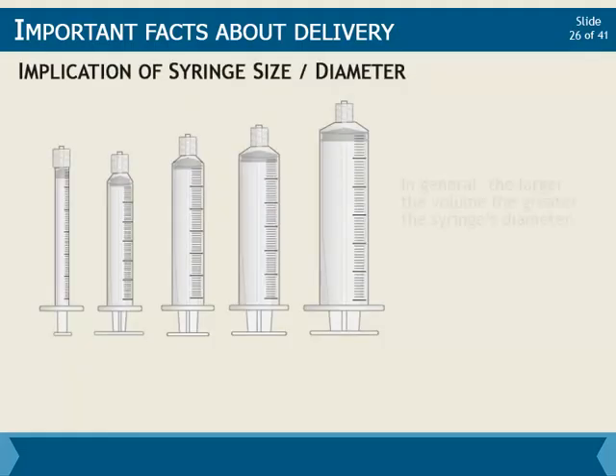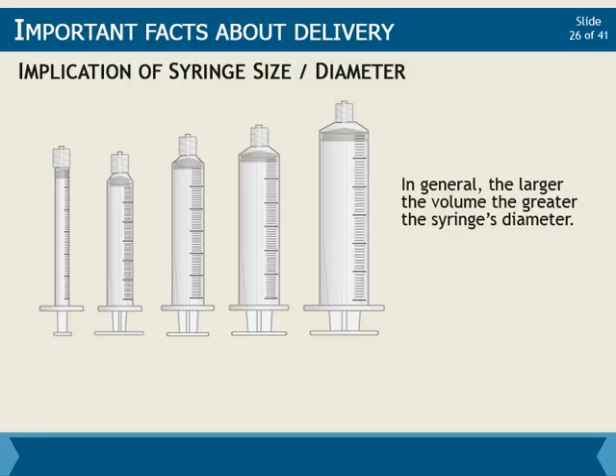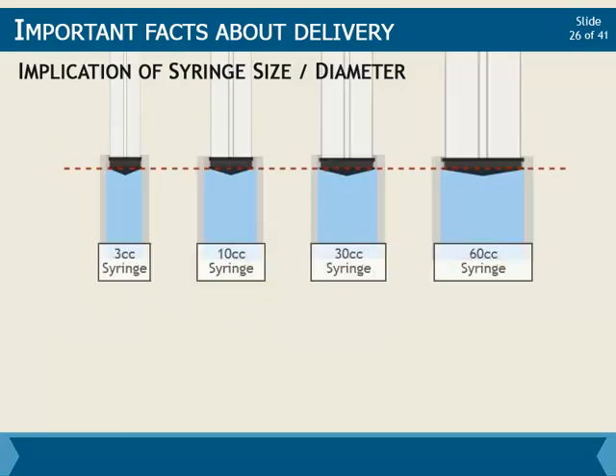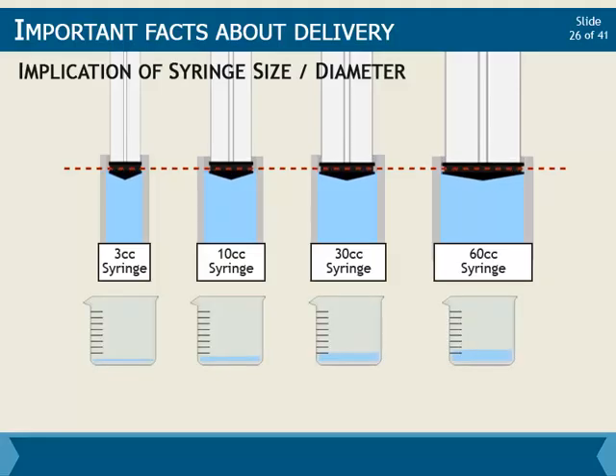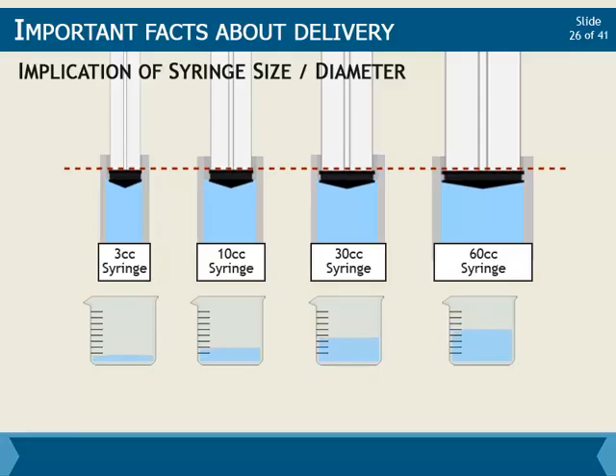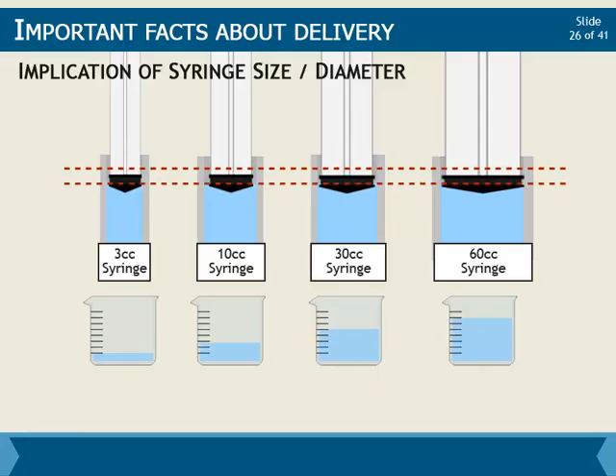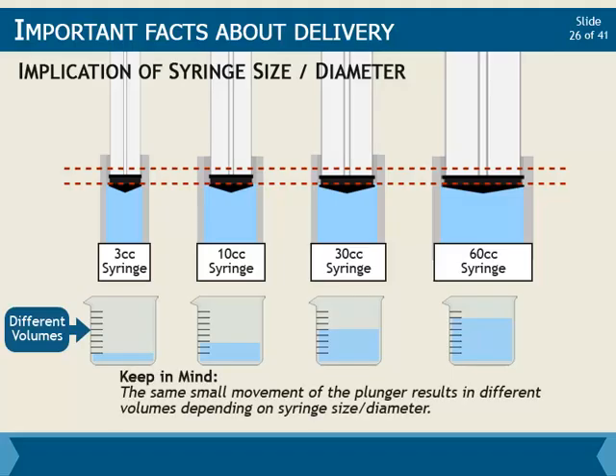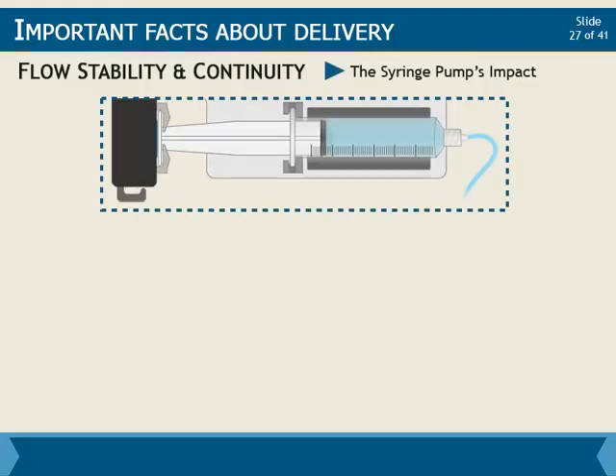Syringes come in different volumes, and in general, the larger the volume, the greater the syringe's diameter. If we take a cross-section of several different sizes of syringes, we illustrate that the larger the diameter, the more fluid that is displaced with each movement of the syringe plunger. The same small movement of the plunger results in different volumes being forced from the syringe. This implication of syringe diameter is important to keep in mind going forward in the module. We will first talk about the syringe pump's impact on flow stability.